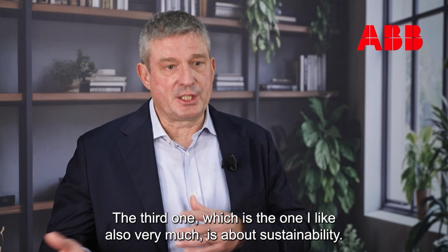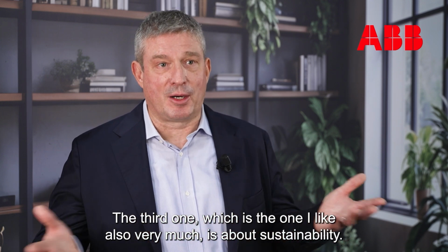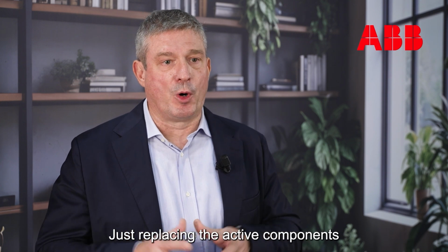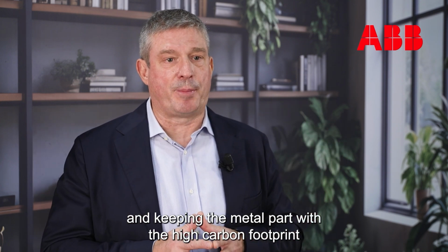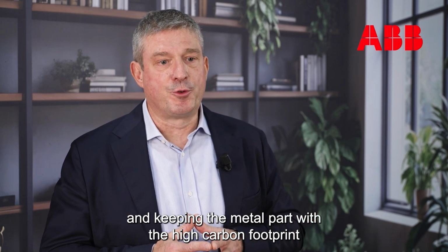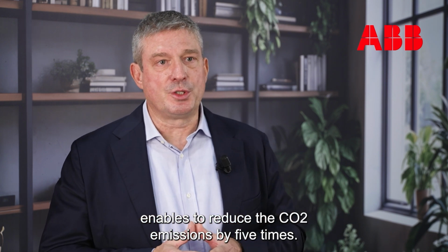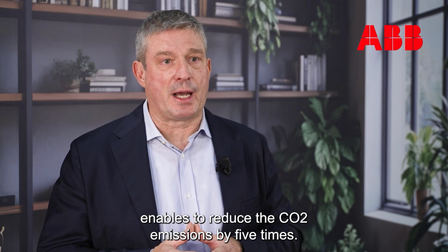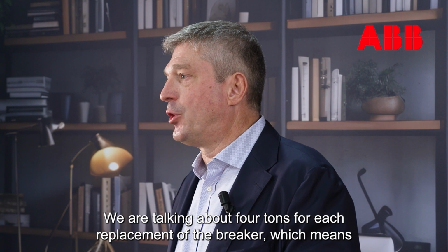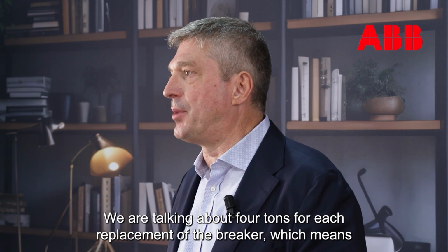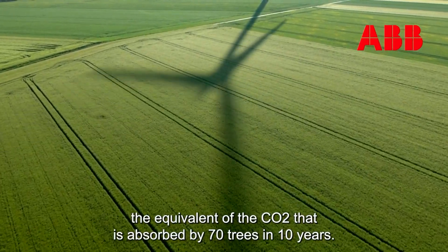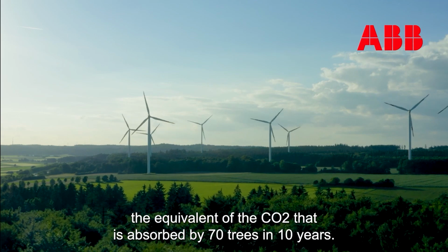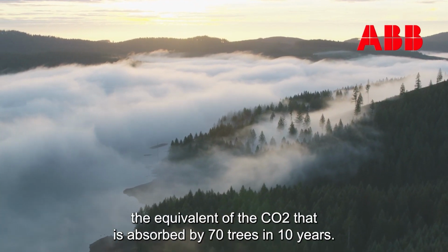The third one, which is the one I like also very much, is about sustainability. Just replacing the active components and keeping the metal part with the high carbon footprint enables us to reduce CO2 emissions by 5 times. We are talking about 4 tons for each replaced breaker, which means the equivalent of the CO2 that is absorbed by 70 trees in 10 years.